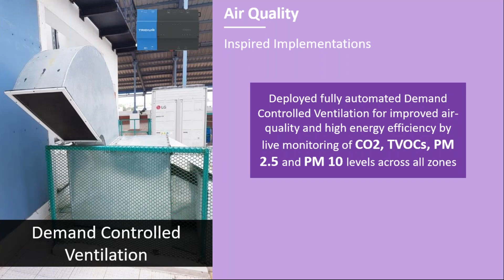Of course, demand control ventilation is in place. Through our building automation systems, we have live monitoring of CO2, VOCs, PM2.5 and PM10, and the ventilation system is controlled based on those readings. Every time the CO2 goes above 800 ppm, the air intake is automatically increased.